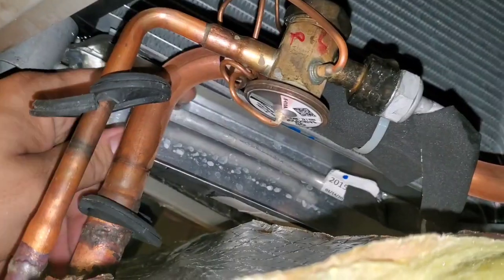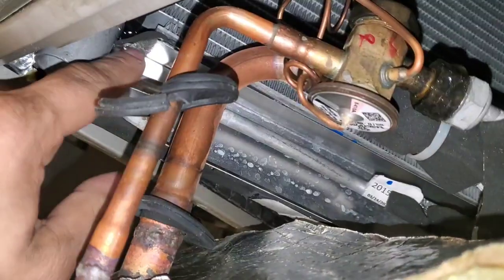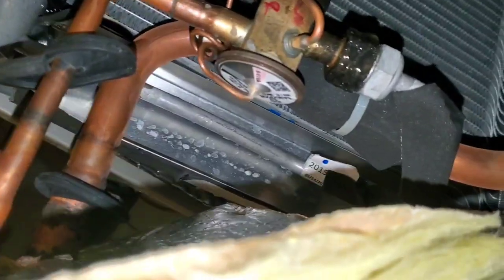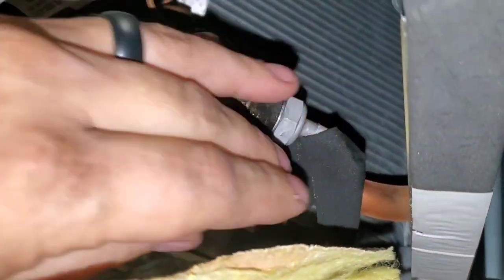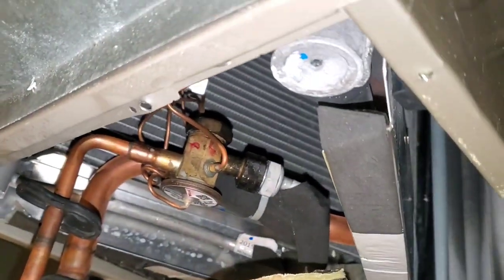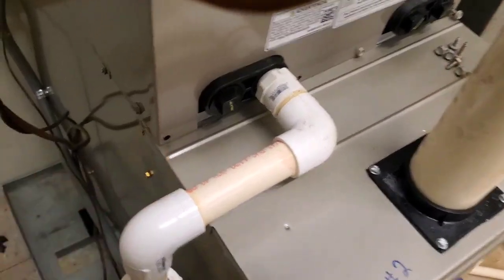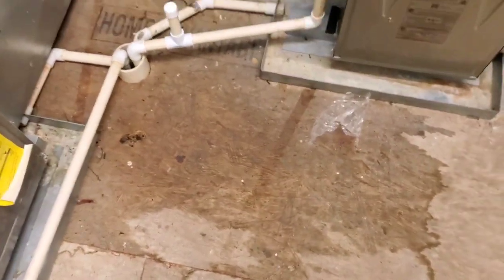Sweat on the suction line. I mean, that one's tight at least. If they're tight, they won't leak. Evaporator inlet, not frozen, wasn't frozen before. No big ball of ice in here or anything like that. If it's running down the side, how come it ended up on the floor instead of in the auxiliary drain pan?